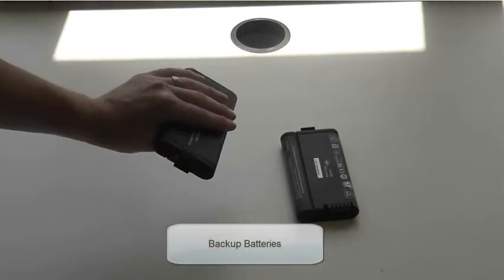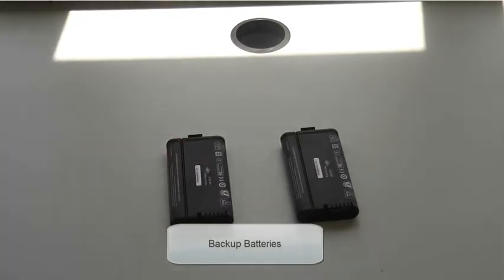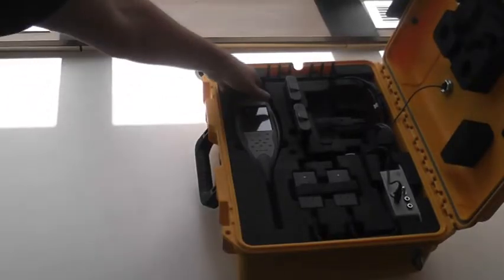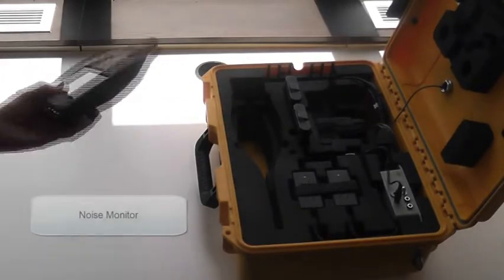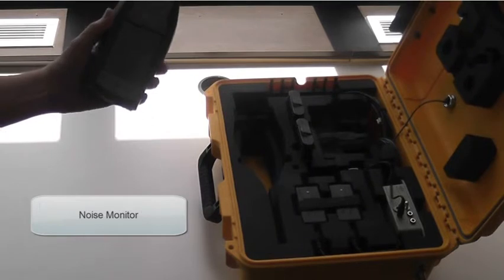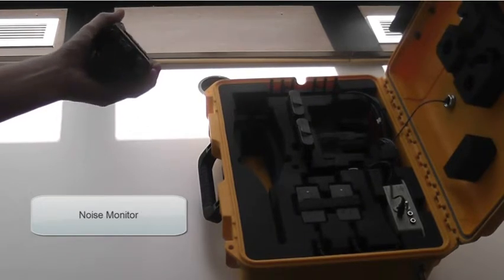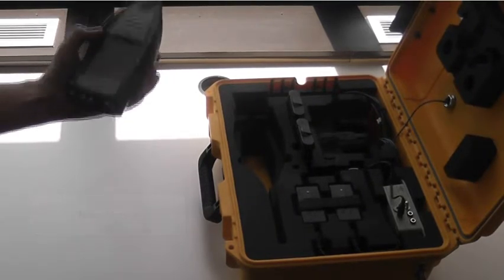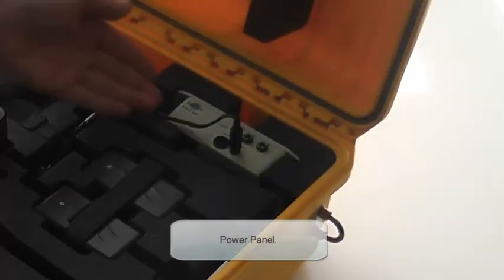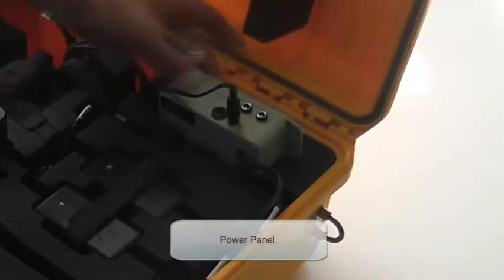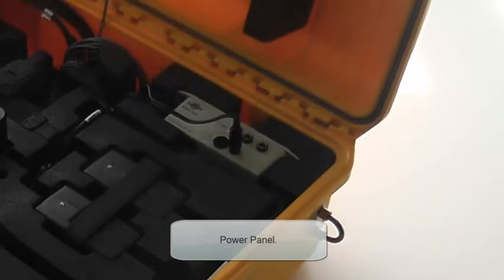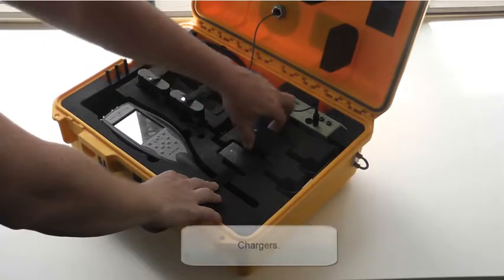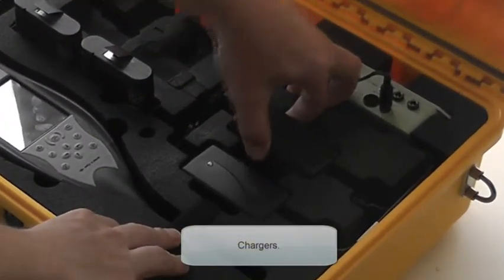Backup batteries are below the router, and when fully charged they'll give you 32 hours of operation. The 2250 noise monitor is at the bottom of the case, but please do not remove it unless absolutely necessary. The power panel is at the top where the unit is activated. Only activate this when everything is connected. Below are the 2 chargers, which will be wired in.